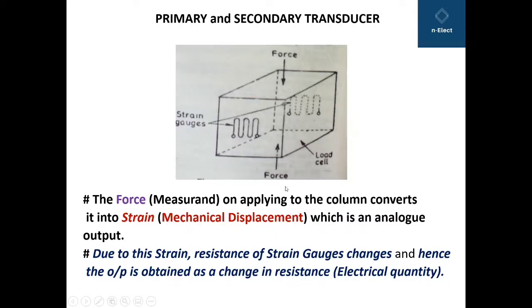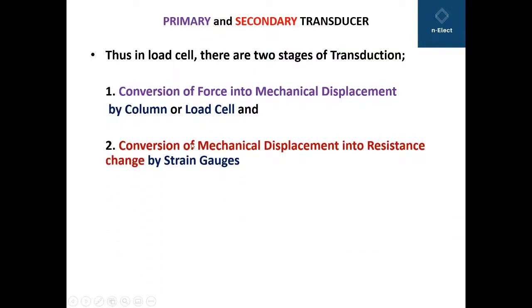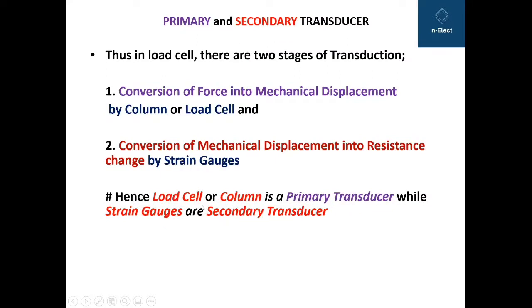In short, the force applied on the vertically opposite faces creates mechanical displacement in the load cell, due to which the strain gauges change their resistance, and the measurement of resistance gives us the measurement of force. Force is converted into mechanical displacement and the mechanical displacement is converted into resistance — a physical quantity converted into an electrical one. Thus in the load cell, there are two stages of transduction: conversion of force into mechanical displacement, done by the column or load cell, and conversion of mechanical displacement into resistance change, done by the strain gauges. Hence, the load cell or column is the primary transducer while the strain gauges are the secondary transducers.